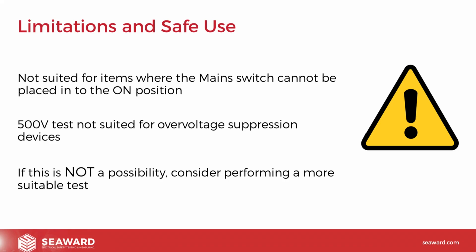So as we've said, for limitations, if it's got overvoltage suppression, then we may not be able to do this test. And again, if we cannot physically turn the unit on, then we may not be able to perform the test. So if the device that you're testing has any of those characteristics, it may not be possible to get a good test, and you should consider performing a more suitable test, either in accordance with, so a flash test or an insulation resistance, followed by one of the mains tests we're about to discuss, or just the mains tests themselves.